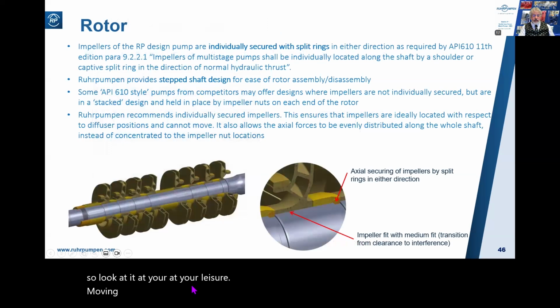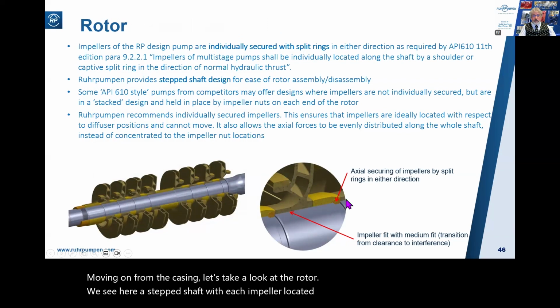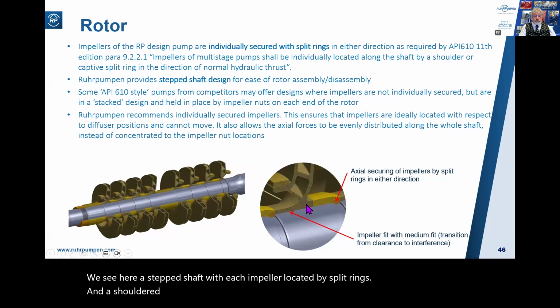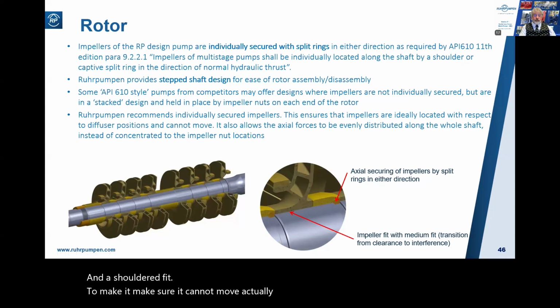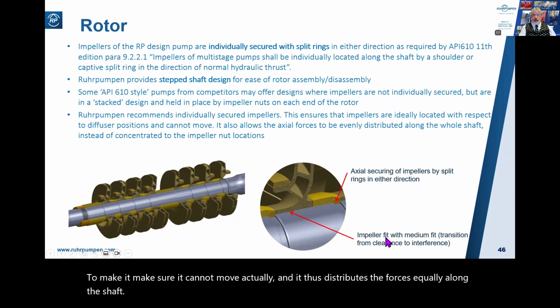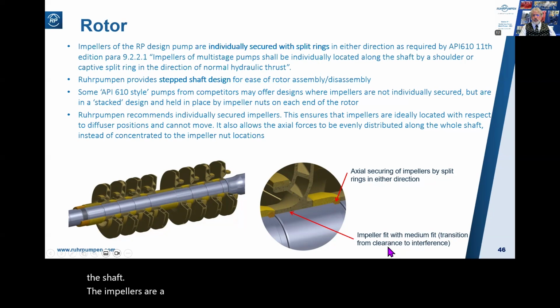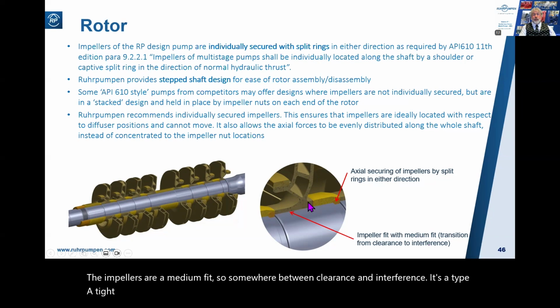Moving on from the casing, let's take a look at the rotor. We see here a stepped shaft with each impeller located by split rings and a shouldered fit to make sure it cannot move axially, and it thus distributes the forces equally along the shaft. The impellers are a medium fit, so somewhere between clearance and interference. It's a tight fit on here without needing to heat it up to slide it on.